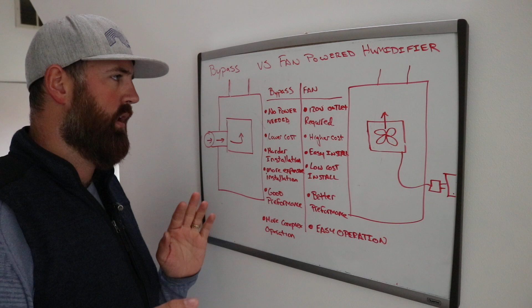If I were planning to install a new humidifier and didn't already have the piping for a bypass humidifier, I would go with a fan-powered humidifier. If you've just got a broken humidifier to replace and already have the piping for a bypass humidifier, maybe just install it since it'll be a bit easier and you've already got everything you need. But if you're installing a new humidifier, building a new home, or getting a new HVAC system, I'd recommend always going with a fan-powered humidifier over a bypass, because of all the advantages we listed.